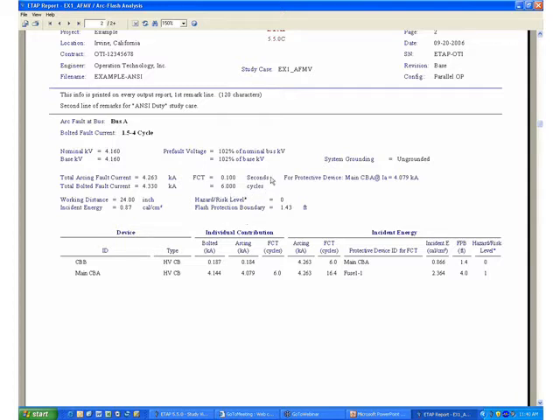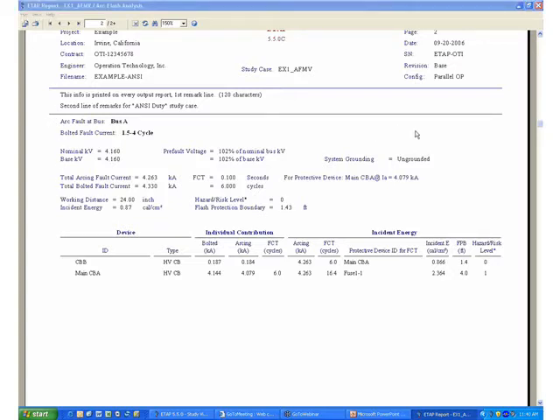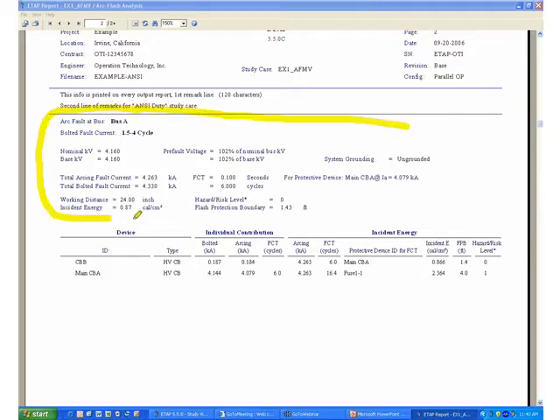Which is operating on the instantaneous region. In this case we have a six cycle operation of the instantaneous setting of the relay protecting this equipment. Therefore the top part of this report will show you all the results for a fault on the bus itself.